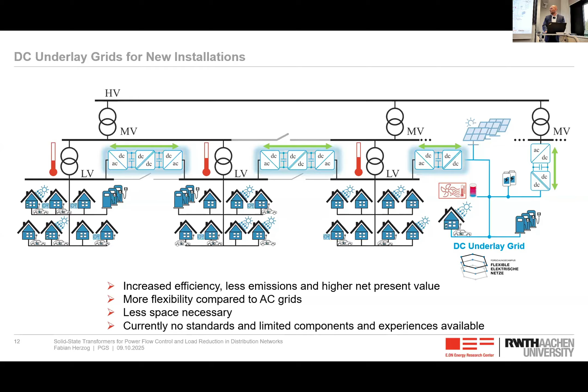To show how the solid state transformer would look for a DC underlay grid, and which components would be omitted - it's basically one of the AC-DC stages. I put some axes here showing which components would not be necessary in such an installation. We can see the size of the solid state transformer can be reduced by about 33%, and the material consumption is reduced even more, because this large LCL filter at the bottom is no longer needed - these weigh very much, I couldn't even lift one up.